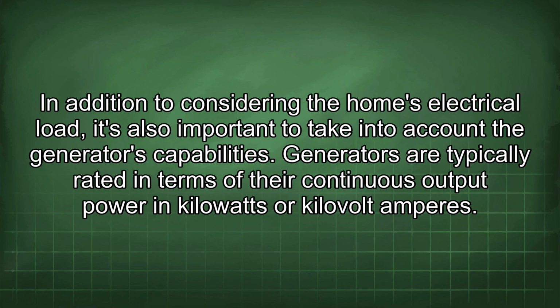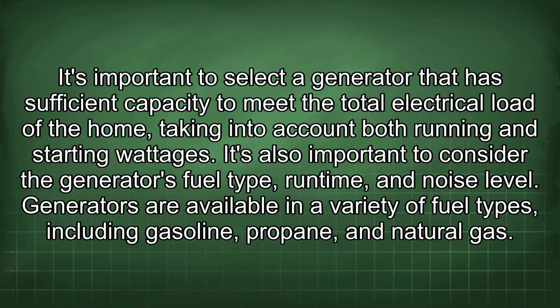In addition to considering the home's electrical load, it's also important to take into account the generator's capabilities. Generators are typically rated in terms of their continuous output power in kilowatts or kilovolt amperes. It's important to select a generator that has sufficient capacity to meet the total electrical load of the home, taking into account both running and starting wattages. It's also important to consider the generator's fuel type, runtime, and noise level.